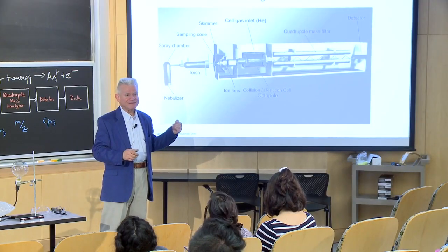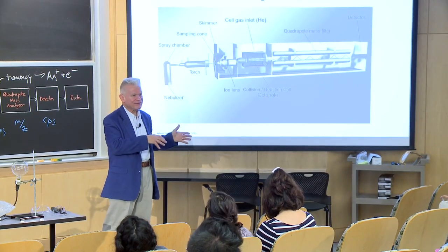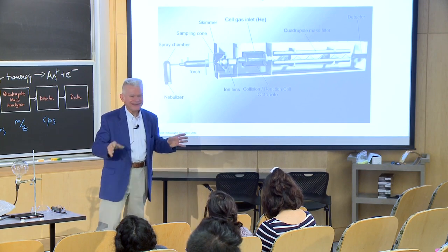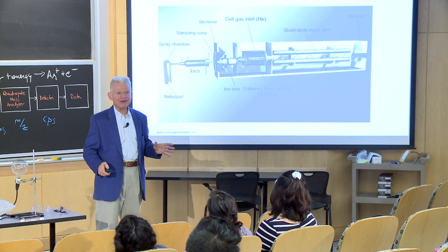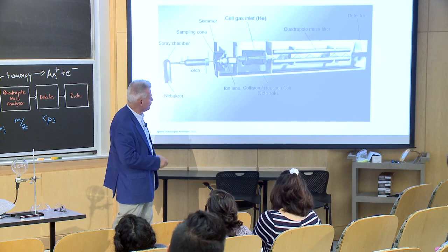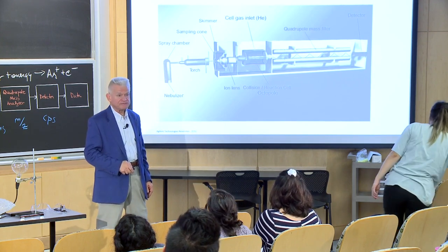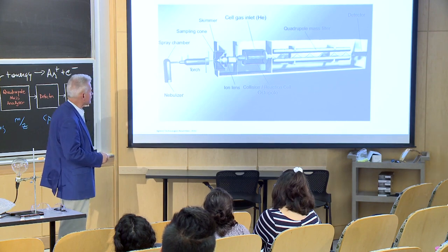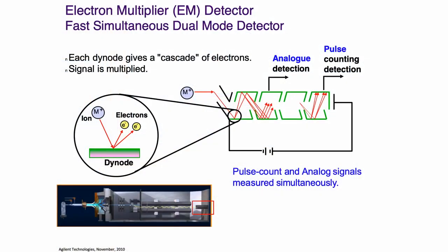This is amazing. I mean, 15 years ago or something, they didn't have this. They had to put equations in for everything. Now at least there's a way to get rid of the polyatomics. So what goes through are the monatomic ions down this quadrupole mass filter toward the detector. This is the detector. It's a pretty fancy detector. It's got these dynodes, which are electrodes in vacuum that produce electrons. They multiply electrons. This thing has 26 dynodes connected together.